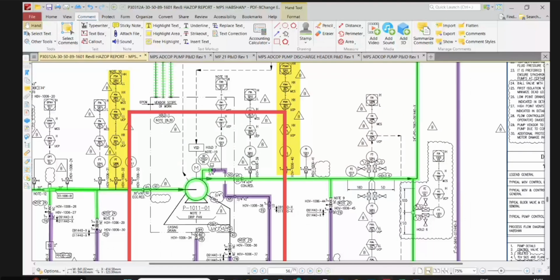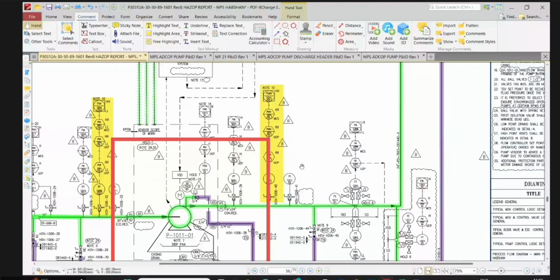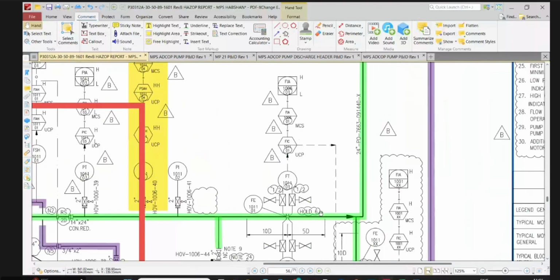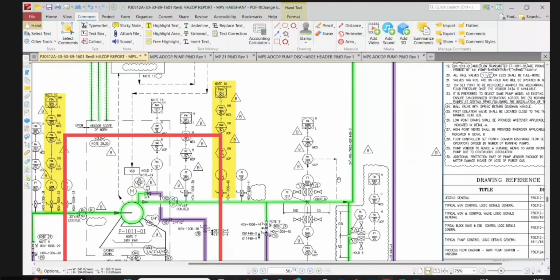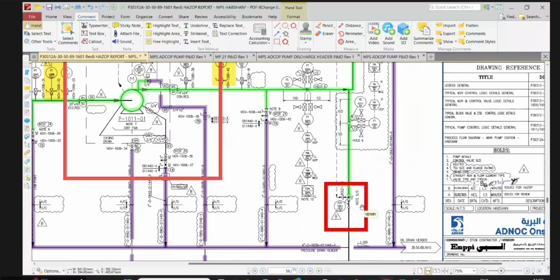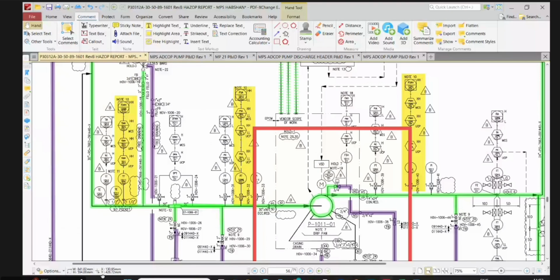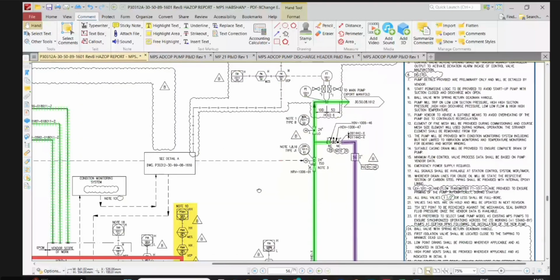Is the pump maximum discharge pressure higher than the design pressure of the piping? No, I think some portion is designed for it, which blockage is there? For this pump, shut-off pressure is higher than piping design. This is a common one. We put some 3 pressure transmitters or something for that, so it is not considered. If the 3 pressure transmitters are there, then we can see it.